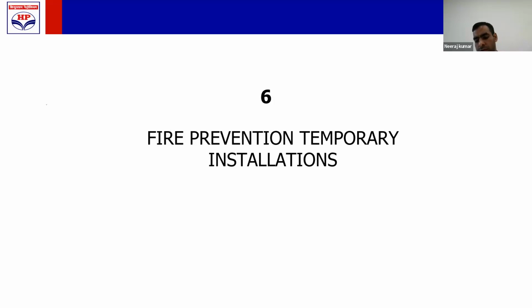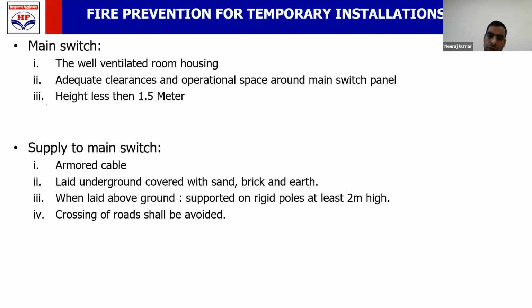What are temporary installations? The installations which are supposed to be in service for less than 6 months will be considered temporary in nature. If you are putting in some power supply for more than 6 months, it should be designed as per the requirements of a permanent installation. Now let us discuss temporary installation. Your temporary installation will have 2-3 things. First, a cable which will bring the power, then a main switching station, and then outgoing supply from that main switching station.